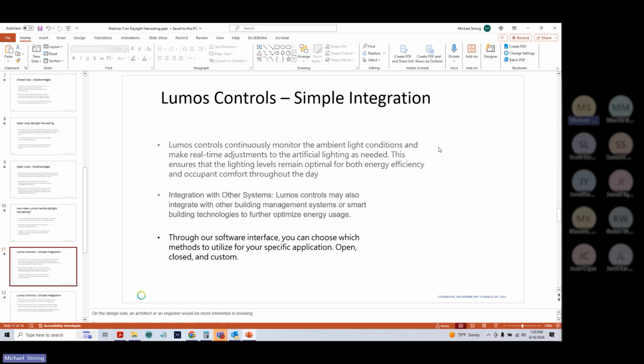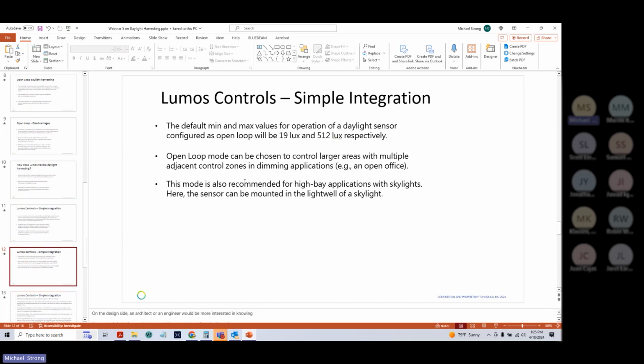We make it simple. We continuously monitor ambient light conditions and make real-time adjustments, as you would expect. Integration with other systems: we also can integrate with other building management systems. As I showed you earlier, we are constantly evolving and trying to make that as simple and as robust as possible. And through our software interface, as I said before, you can choose open, closed, or custom. If you choose the open loop method, 19 lux to 512 lux is the open loop default min and max values.